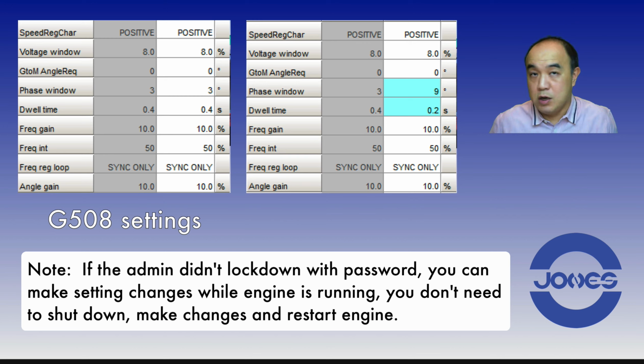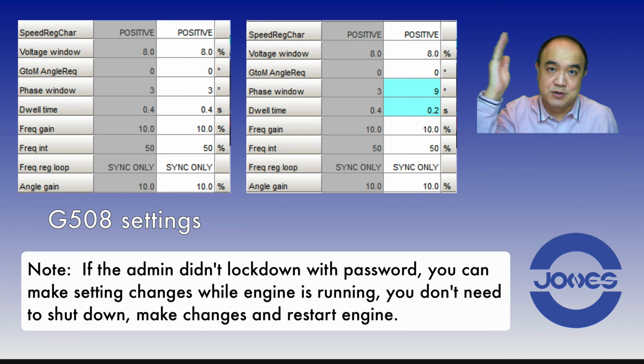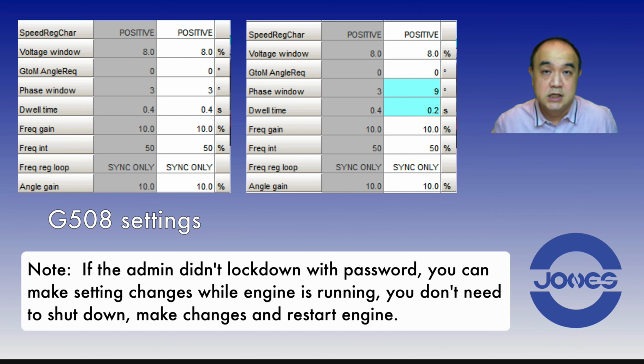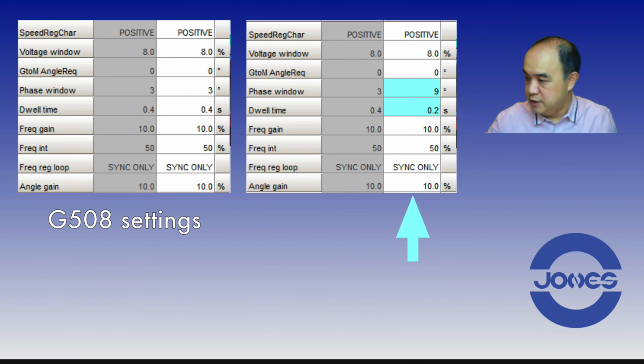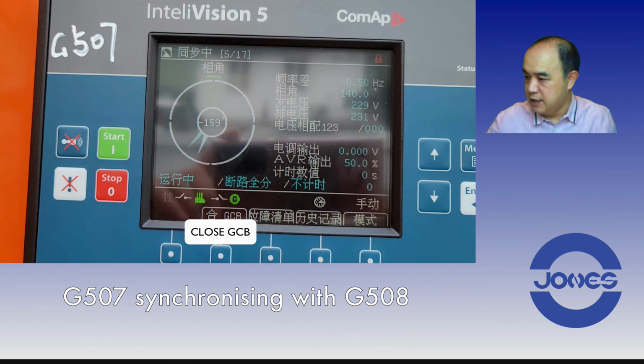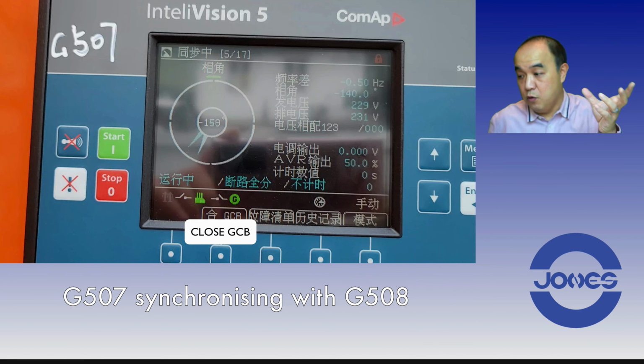And I wanted the dwell time to be shorter because the engine was going up and down in speed, so I didn't want it to hold for too long, so I shortened it to 0.2 seconds, as you can see in my settings. So these are my settings. Now, we can see after I changed the settings, G508 is online. You saw how it was hunting up and down.